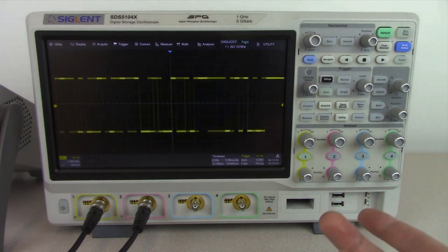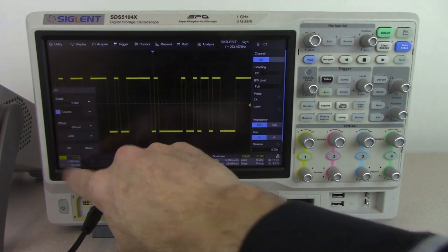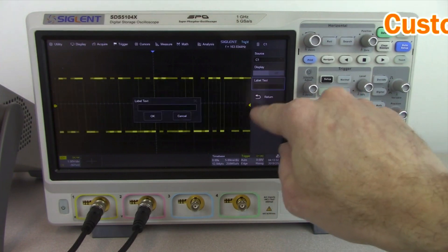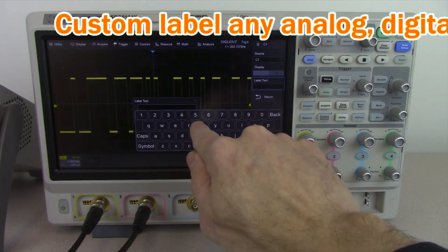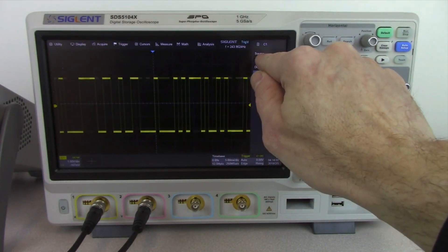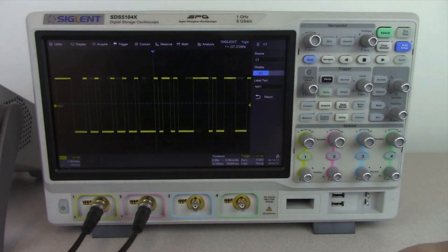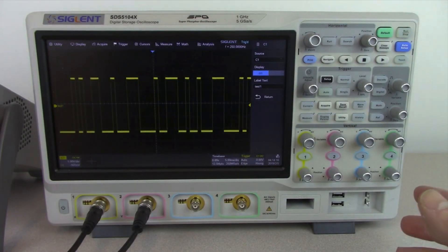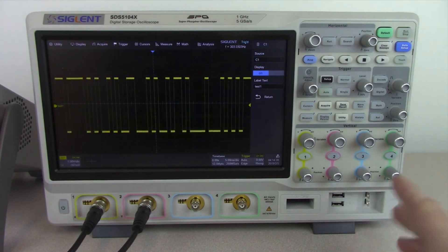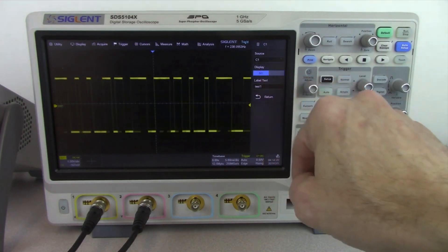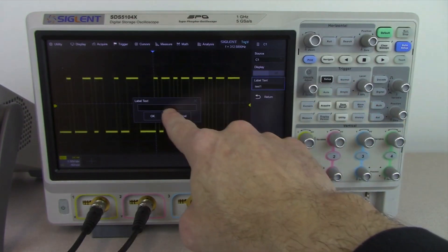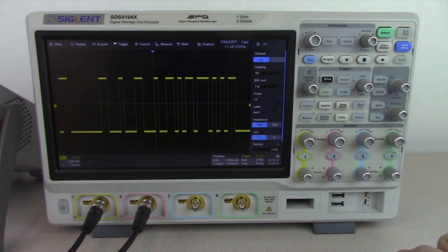One of the new features of this oscilloscope is channel labeling. We can bring up one of the analog channels — I'm just going to press on that channel and you'll see the menu pops out. We can go to label and type in label text; I'm just going to put 'Test 1' and hit enter. So now our text shows up and we can rename channel C1 to 'Test'. We can label each one of our analog channels, digital channels, or math channels. This is very helpful if you're doing test reports with multiple channels and trying to remember what each channel represents.